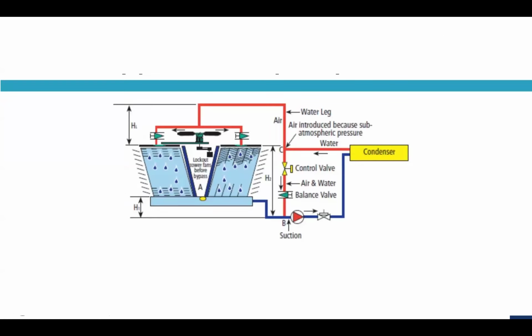Kind of unusual, where I might have an open system, and then I take into account, say, that elevation. That static would be like a cooling tower, where I have a pump at the base, below the basin. So there might be an actual positive suction head here, but now I have to lift that water, if you will, up to the high point here to my spray nozzles or my fan. So what is my vertical height minus my basin height? When I account for that pump selection and I have some piping flow rate, frictional resistance I have to design and account for, I also have this vertical height that I always have to account for to get that water to that high point.